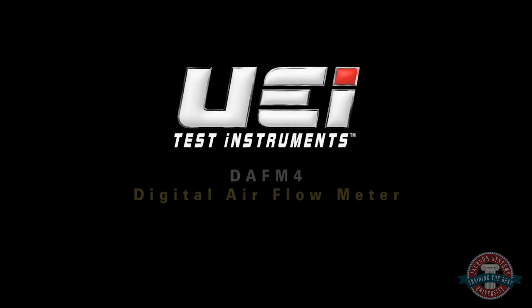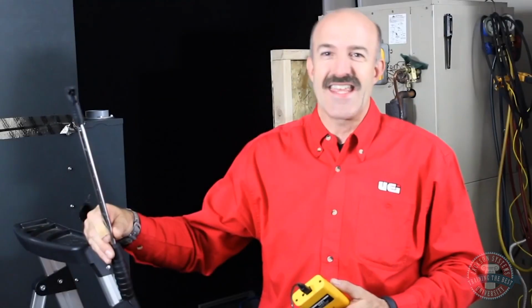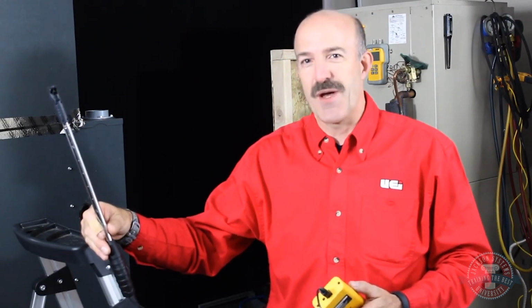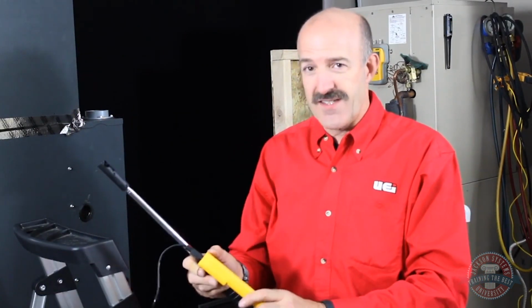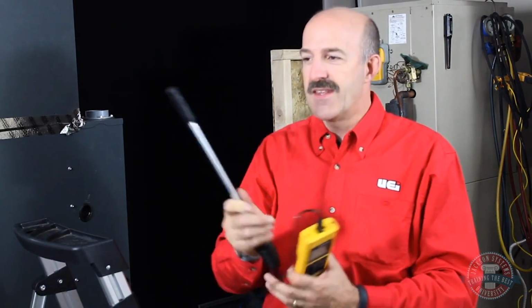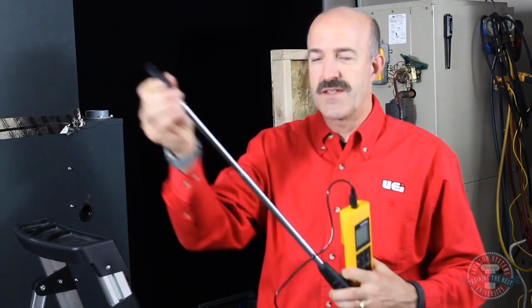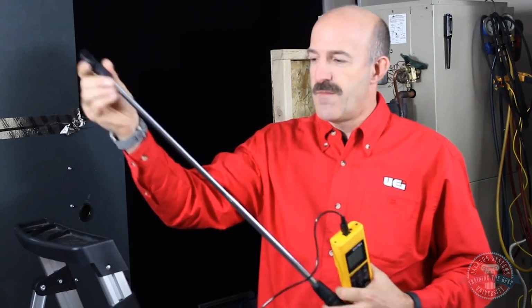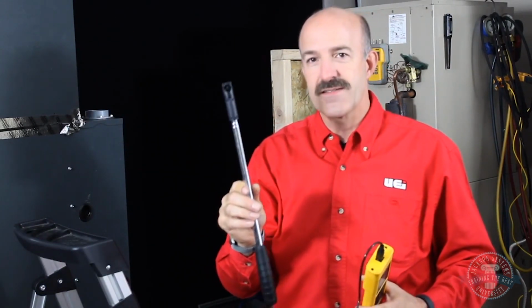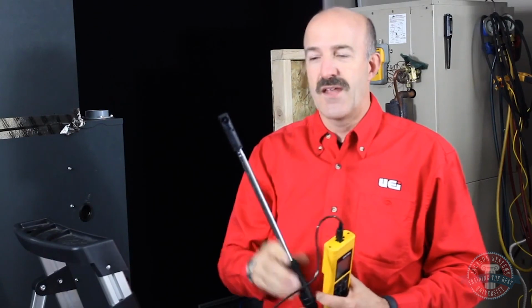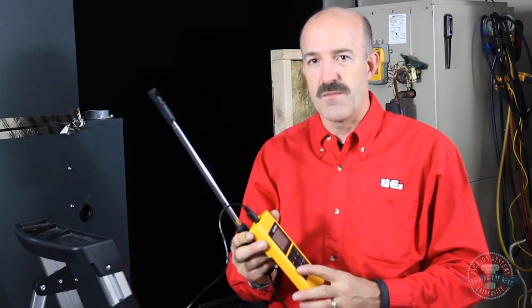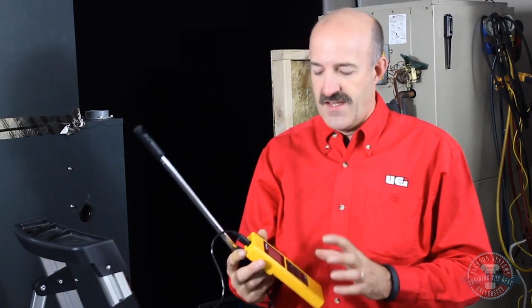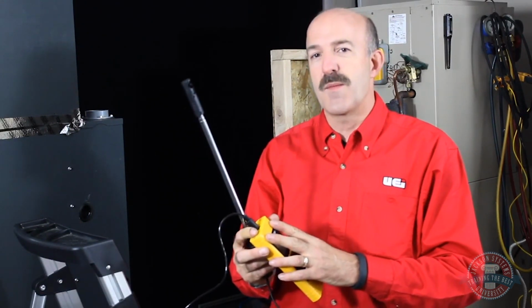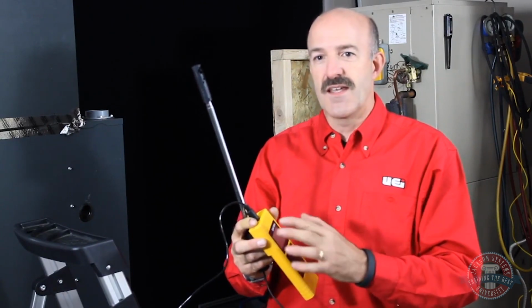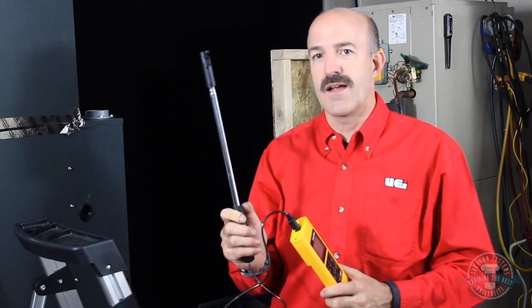Hi, my name's Dave with UEI. Today I'll be conducting an introduction to the Induct DAFM4 vane anemometer. This tool comes packaged in a hard carrying case and includes the handset and a small vane anemometer that extends to 39 inches. Measurements include air velocity, temperature, and relative humidity, and from those it can calculate dew point and wet bulb, as well as air volume in CMM or CFM. The base also allows you to do a timed average up to 99 minutes to get a good average over the surface or in a duct.